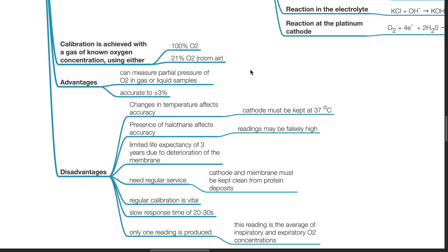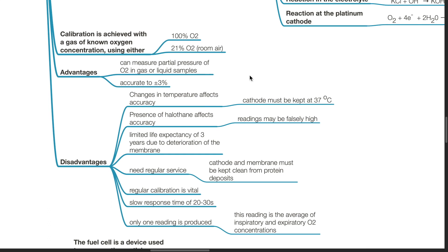Advantages of the Clark electrode: it can measure partial pressures of oxygen in gas or liquid samples, and is accurate to ±3%. Disadvantages: changes in temperature affect its accuracy, and the cathode must be kept at 37 degrees Celsius. The presence of halothane affects accuracy and readings may be falsely high. It has a limited life expectancy of 3 years due to deterioration of the membrane.